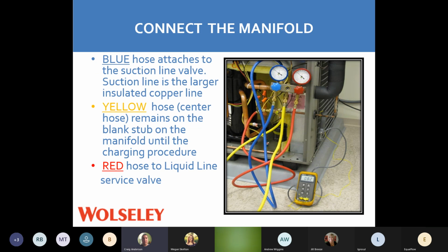So connecting our manifolds to our outside, our blue hose is going to our suction line, which is our larger pieces of copper. Our yellow one is going to our vacuum pump, or it's going to our charging cylinder, where our charging cylinder is sitting on our scale, because that's the only way we charge it, correct? Red hose is going to our liquid line service valve. So we're ready to go.